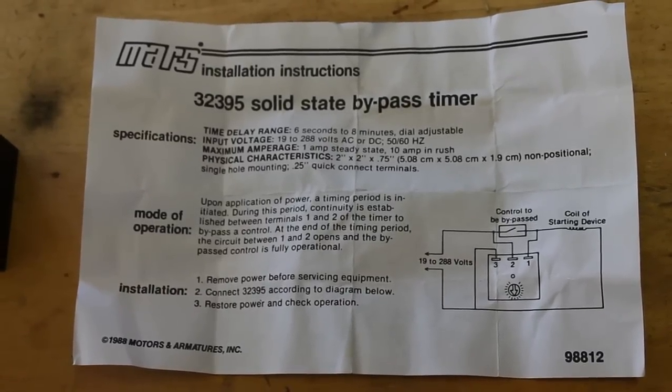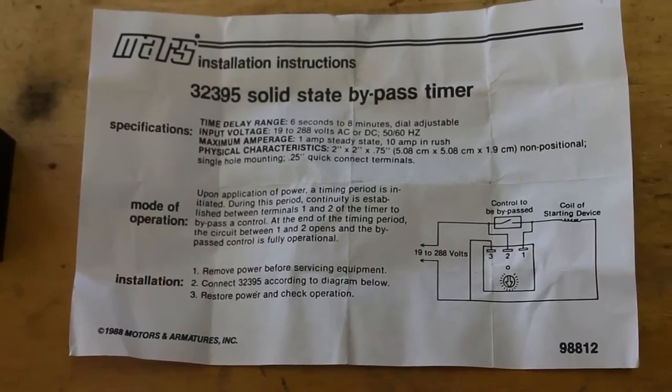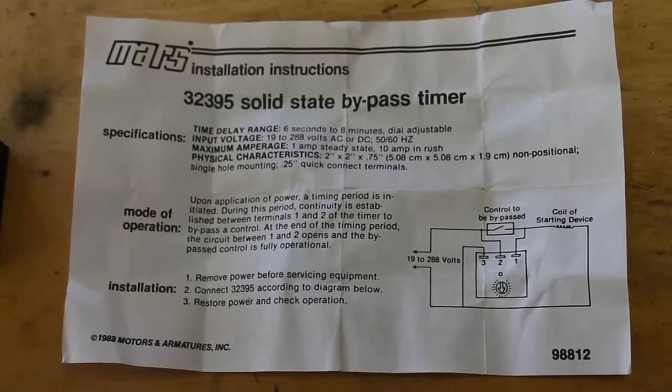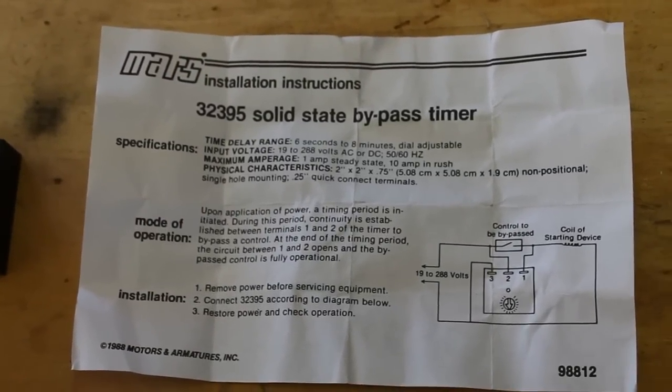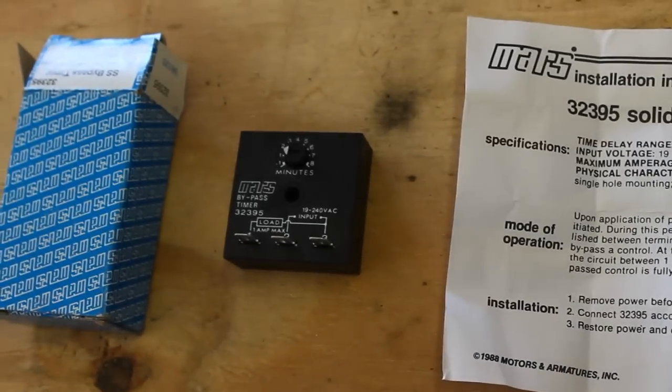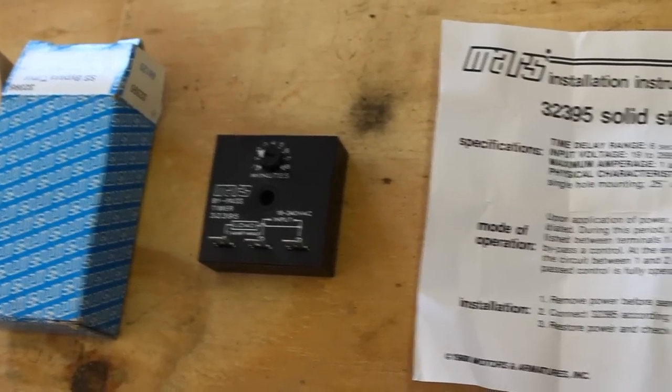The suction pressure will often dip very low then rebound as the machine runs. We don't want to trip a switch every time we have a startup. This relay will allow us to bypass that safety for a certain period of time while our unit starts up.